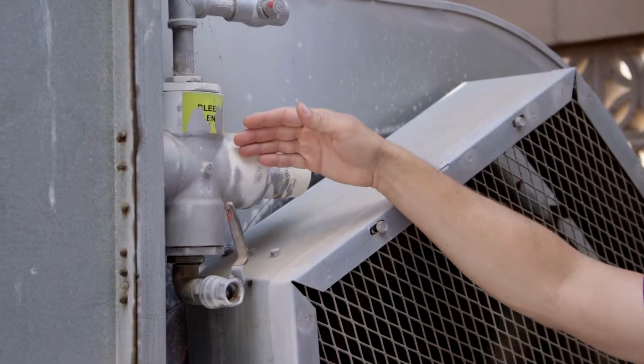The first thing you want to do is make sure you have a clean system. To have a clean system, follow the SOW and clean your cooling tower as required. The second thing you want to do is make sure you maintain a free chlorine between 1 to 1.2 ppm. The third thing I want to review is dead legs.